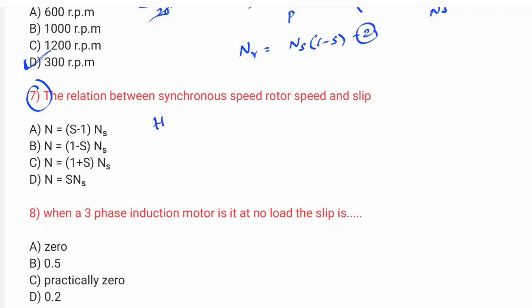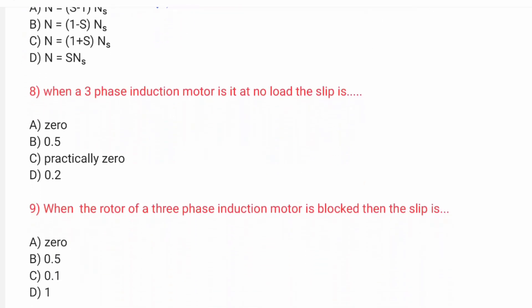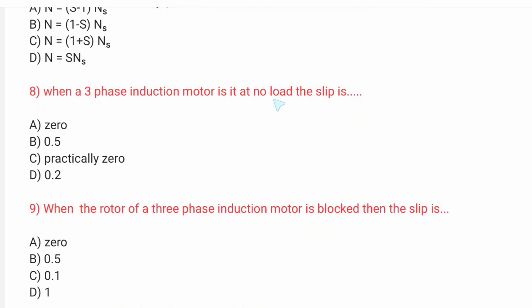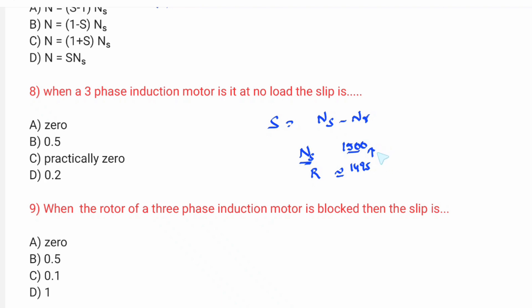If you have any questions, you can answer in the comments. Next: the three-phase induction motor is at no load. At no load, the slip is nearly zero. The rotor speed is nearly equal to synchronous speed — for example, nearly 1495 RPM when synchronous speed is 1500 RPM.